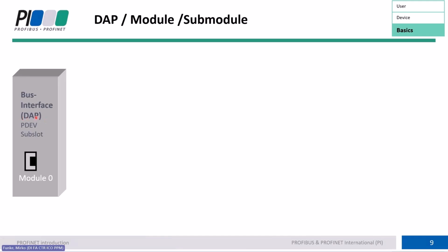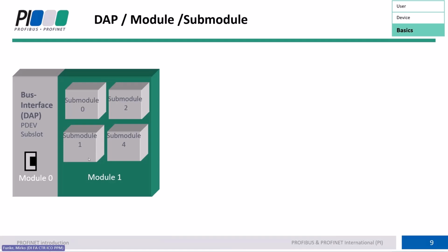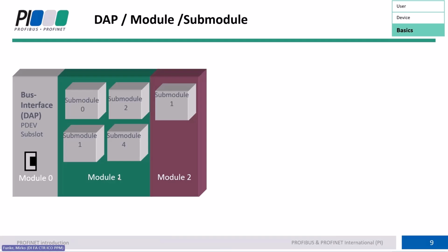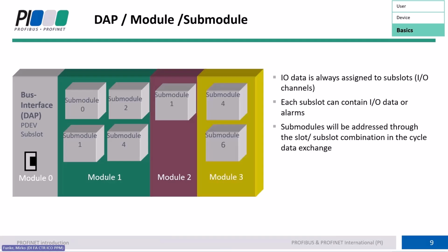This is the device access point DAP, and this is something you will also find afterwards in your configuration file, such called generic station description, a GSD file that you need to configure for or need to set up for your device. And this is the common understanding what is implemented then by the engineering system. And then we add in modules our information. That means we have several modules. At least one is required. And in each module, we have submodules.